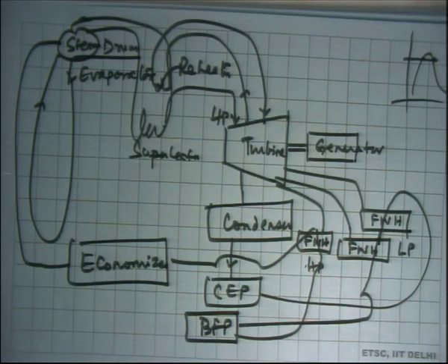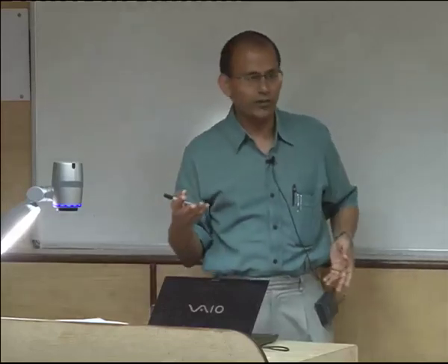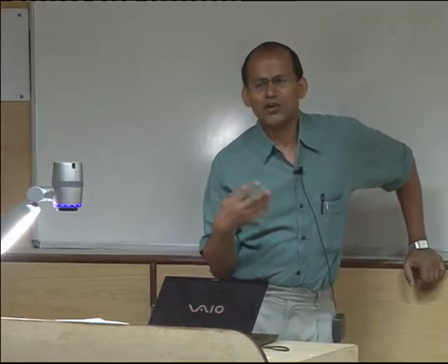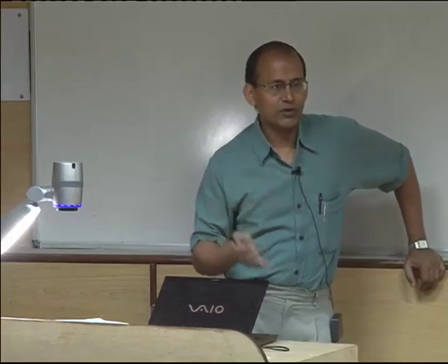So this circulating pump for condenser cooling water needs to handle a huge flow rate but a small head, because the pressure head is only given by the pressure drop in the length of the pipe, which is a couple of kilometers, of course, from the cooling tower to the power plant, but that's not going to be very large. It's not going to be 200 bar.